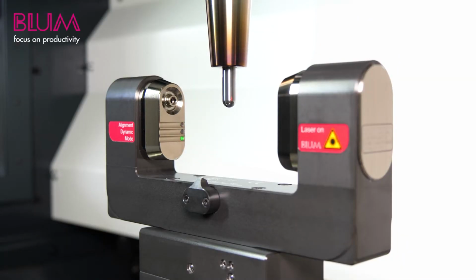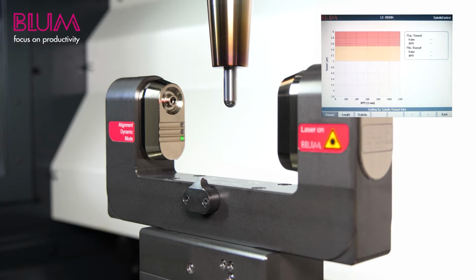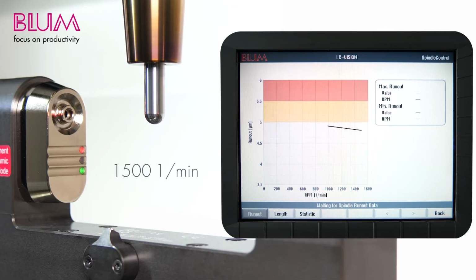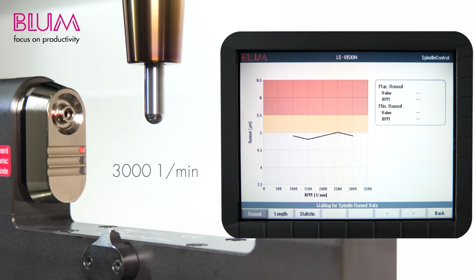In the following video you can observe a concentricity check that is carried out for the entire speed spectrum of the machine. Here, the reference tool is positioned in the laser beam first of all, then the speed is gradually increased. The laser determines the dynamic change in the reference tool at the selected speeds. If deflections are visible, this could be an indication of a defective ball bearing in the spindle.